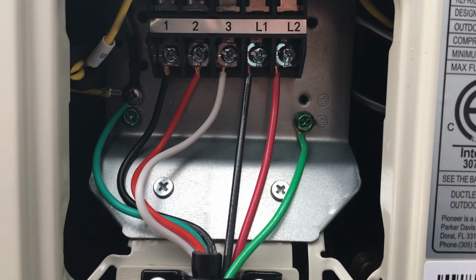Like on the indoor unit, I just didn't have a good way to get my camera into a good position to film the wiring connections. The L1, L2, and grounding terminals on the right are for the power from the disconnect box. The 1, 2, 3, and ground terminals on the left are for the signal wire to connect. It is vital that the red, black, and white wires from the indoor unit connect to the same terminals on the outdoor unit.